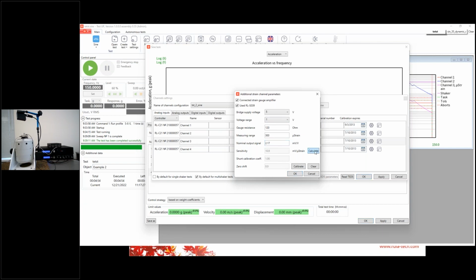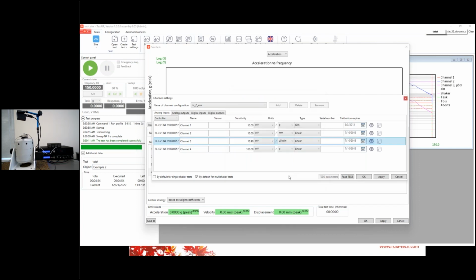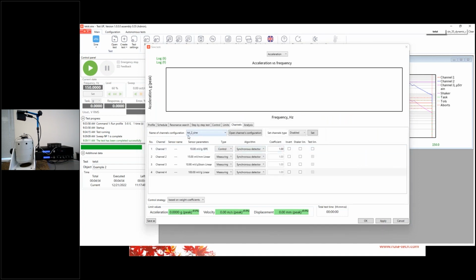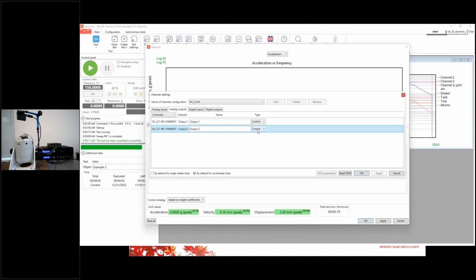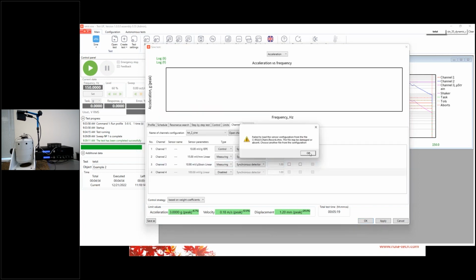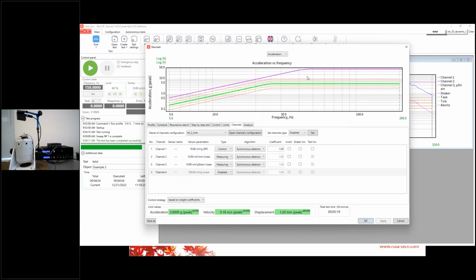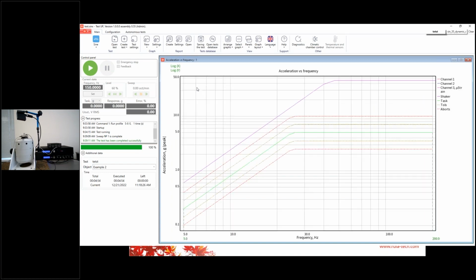After that, we press calculate, and here you see that our sensitivity is 10.9 millivolts per strain. We press OK, and here you see that's our strain gauge sensor. Let's apply settings and press OK. Here you see that it's selected 10 millivolts per G IEPE, its control, 10 millivolts per millimeter, and our strain gauge sensor. After that, we need to disable the fourth channel, and let's apply the settings. Oh, I think we have two outputs. Let's disable it. Yes. Here you see our profile. And now I think we're ready to run the test.